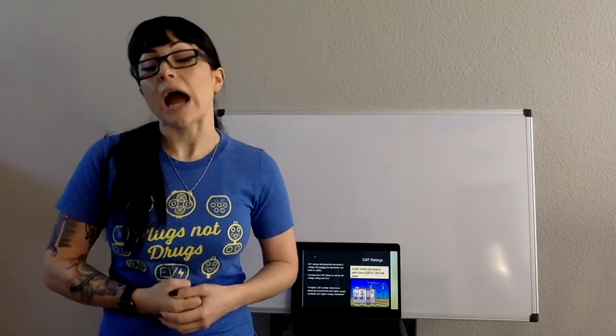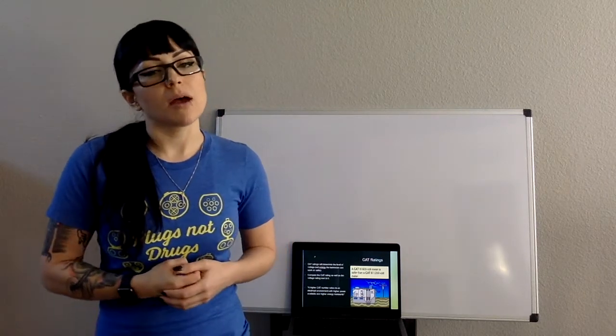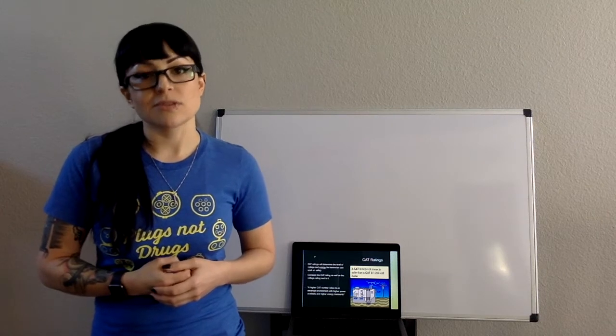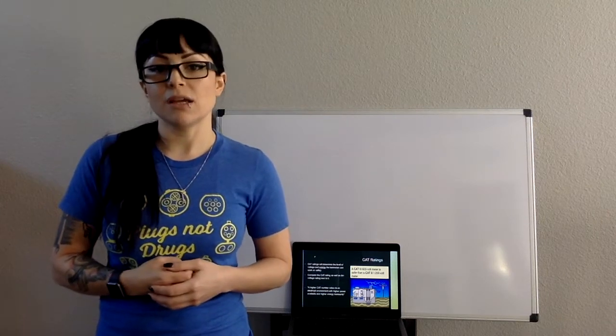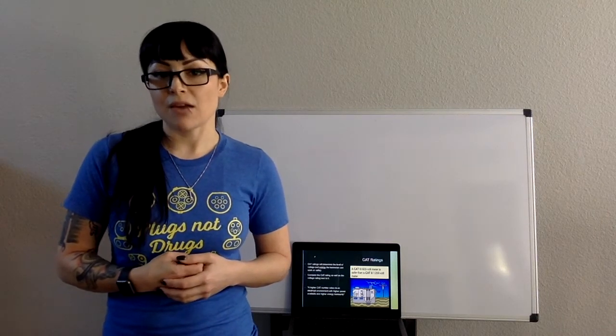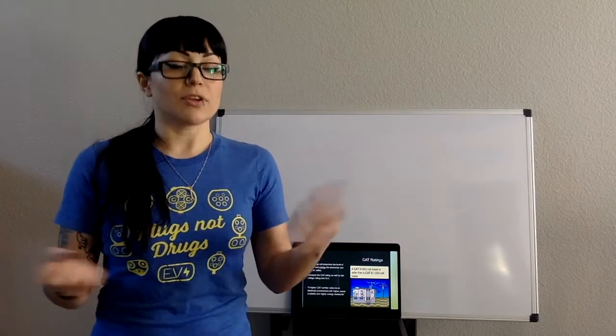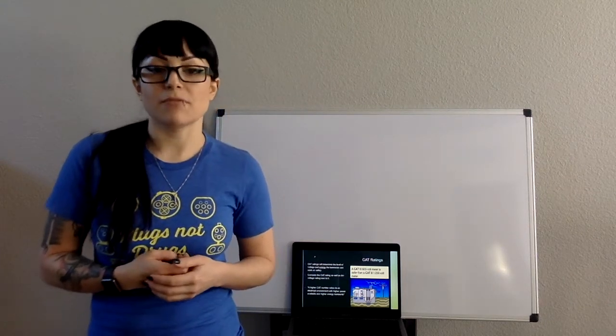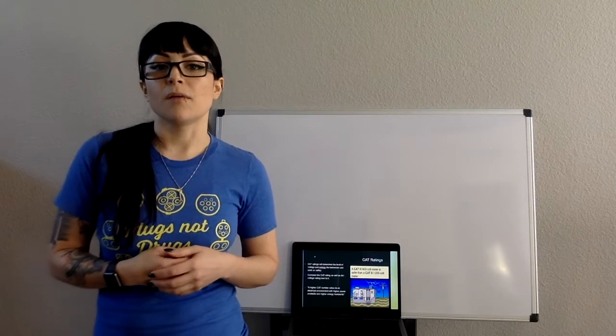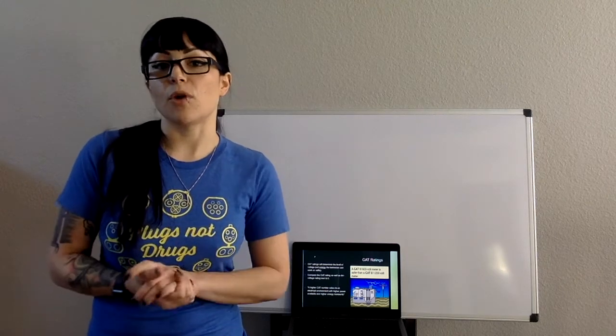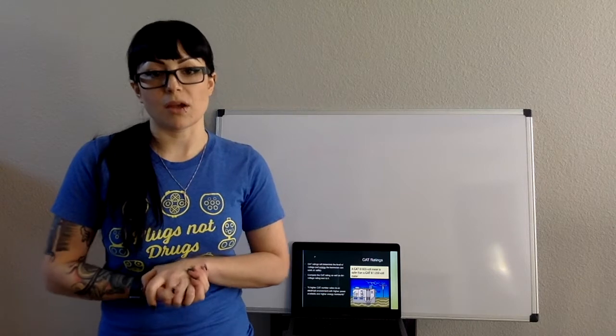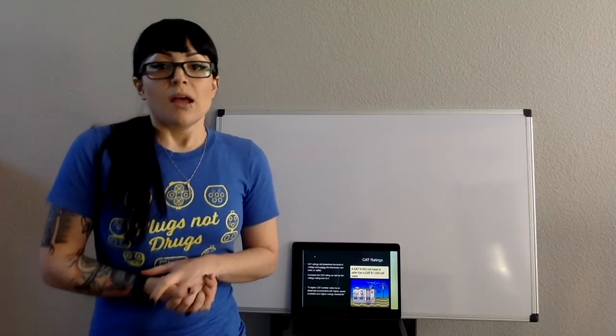If you're working on hybrids, the minimum you want to use is a category 3. You don't necessarily need a category 4, but you can use one if it's already rated for that - no problem. You're going to want at least category 3 if you're working on high voltage systems.